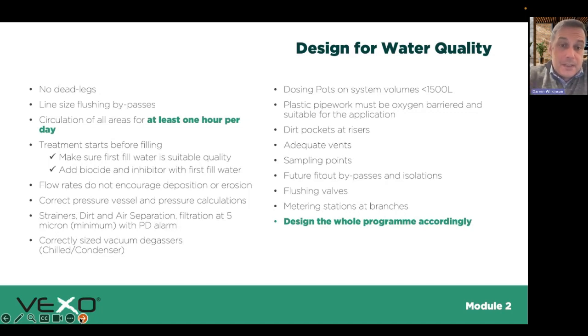Make sure the flow rates do not encourage deposition or erosion. So typically we want to be above 0.5 meters per second, and we don't want to be above the CIBSE guide in terms of maximum flow rates per pipe diameter. Make sure we've got the correct pressure vessel. Really important. We see many system failures, and then it turns out the vessels themselves haven't been sized correctly. And of course, when the system's operating, it starts drawing in oxygen.